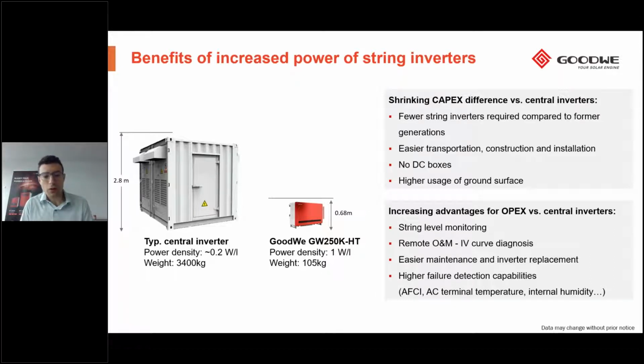And with this trend of increasing power, of doubling the power of the string inverters, now we are shrinking the difference of capex, of initial investment, compared to central inverters. And historically, this has been the main advantage of central inverters. One of the main advantages is of course the initial investment cost. And now with increasing power of the string inverters, we do require only fewer string inverters in one installation compared to the past. And the other advantages of string inverters, such as easier transportation, construction, installation, also integrating different components, especially on the DC side, and having a better usage of the ground surface, all add up together to decreasing this capex difference compared to central inverters.